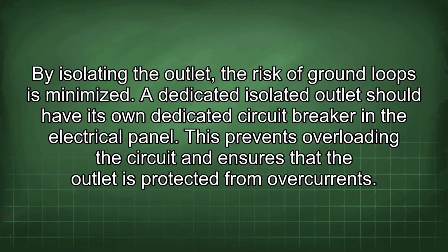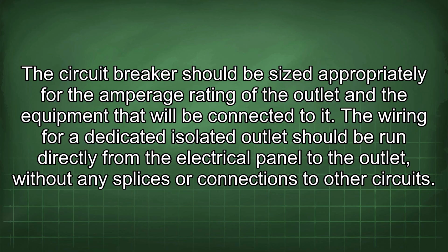A dedicated isolated outlet should have its own dedicated circuit breaker in the electrical panel. This prevents overloading the circuit and ensures that the outlet is protected from overcurrents. The circuit breaker should be sized appropriately for the amperage rating of the outlet and the equipment that will be connected to it. The wiring for a dedicated isolated outlet should be run directly from the electrical panel to the outlet, without any splices or connections to other circuits.